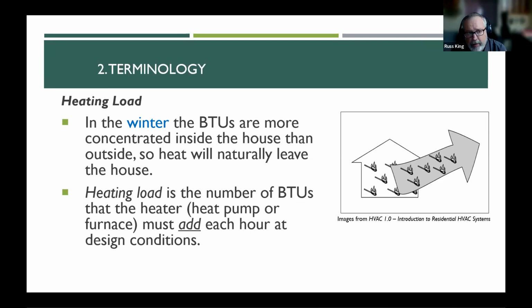If you don't do a cooling load and a heating load, you're just guessing, and unfortunately that happens way too much. A lot of people just say, how big is the house? There's this old rule of thumb out there, 500 square feet per ton. So a 2,000 square foot house divided by 500 is 4 tons, the perfect size for a 4 ton. That's not how it works. The load of a house is way more dependent on glass area and glass direction than on the square footage. A very small house with a lot of glass will actually have a higher cooling load than a big house with a little bit of glass. So basing sizing of equipment on the square footage of your house is a bad idea, but it's way too common.